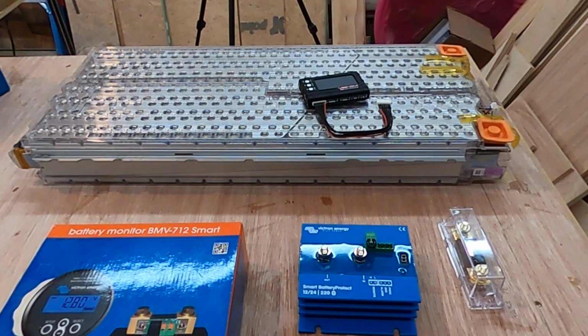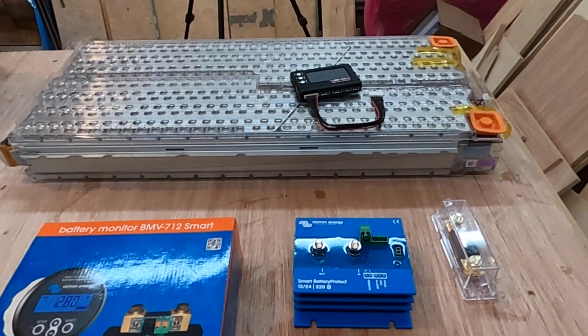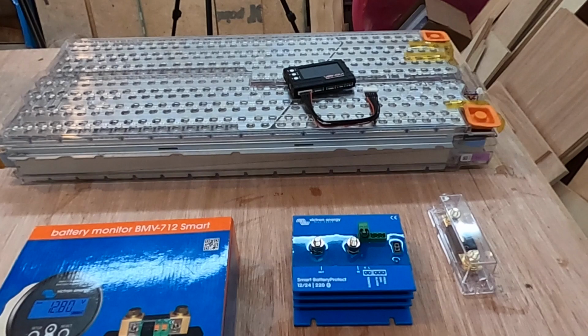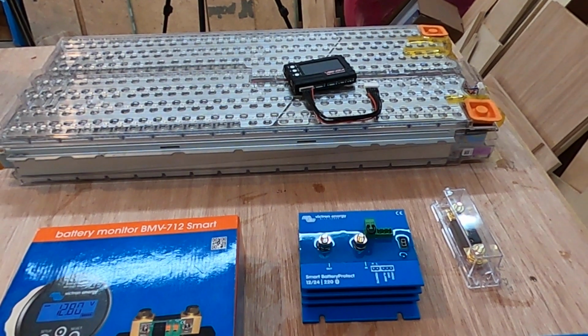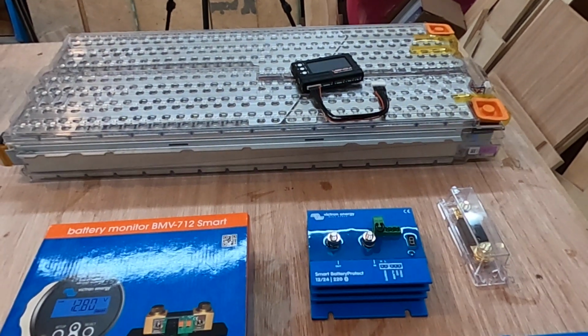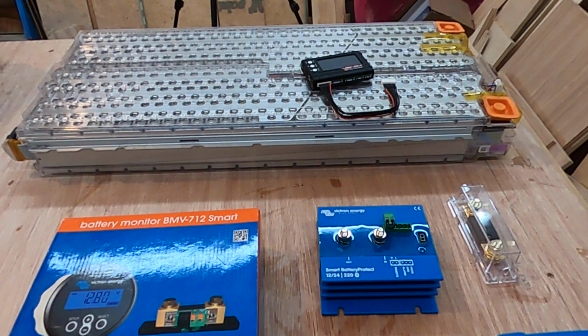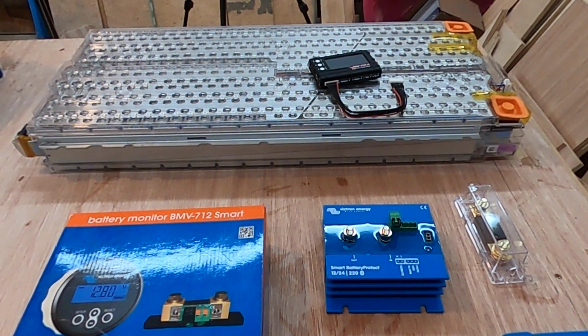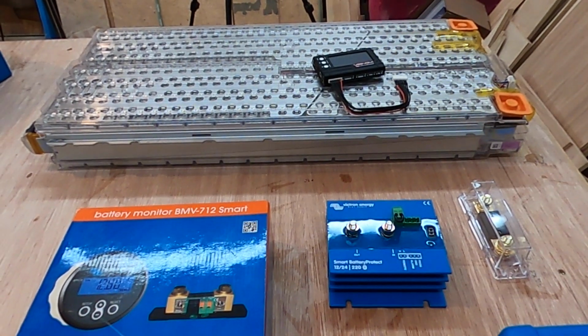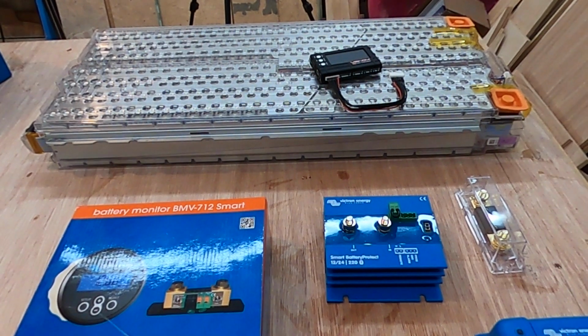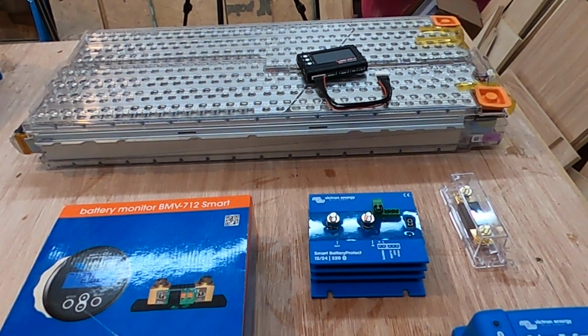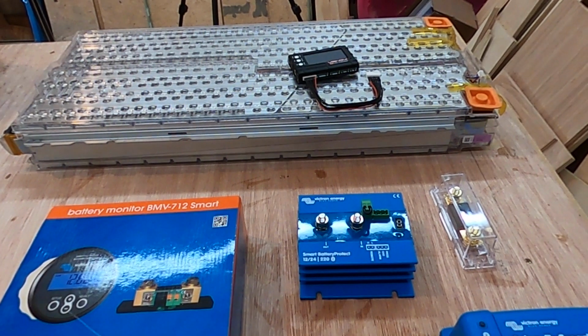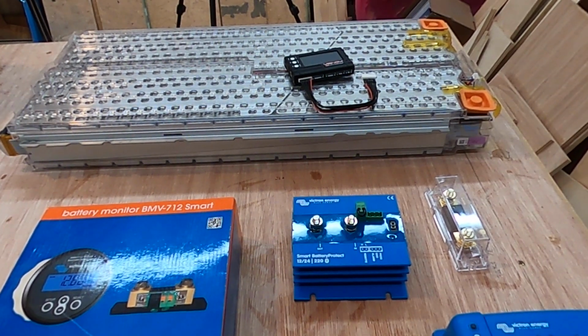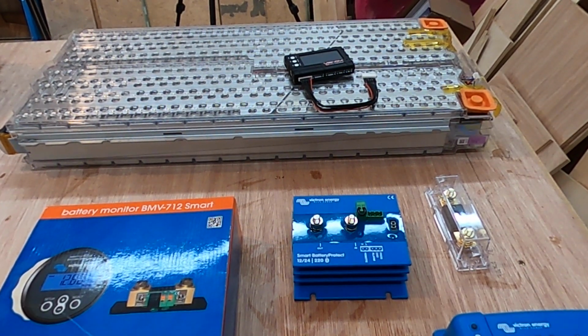After filming this video, we've done a little bit more research on our battery module, and it turns out we're going to use a 250 amp fuse in this location. Reason being, if you're discharging at a rate higher than 250 amps, the Tesla battery module has the requirement that it needs to be cooled. You'll exceed the thermal limits of the pack, and that's not a good thing - you'll melt it down and could potentially start a fire.